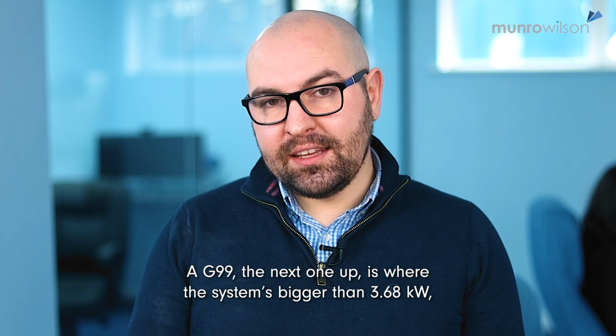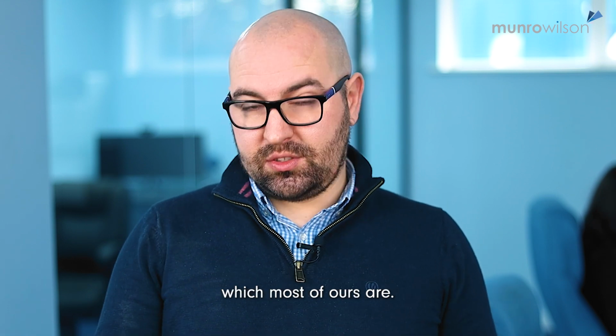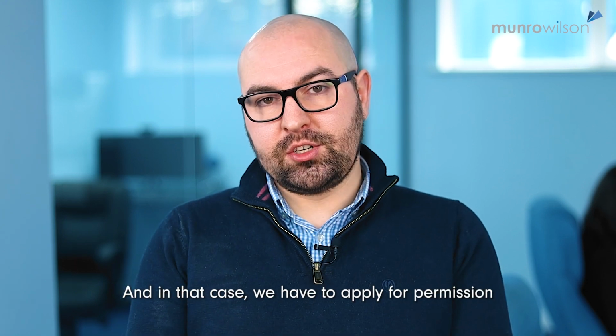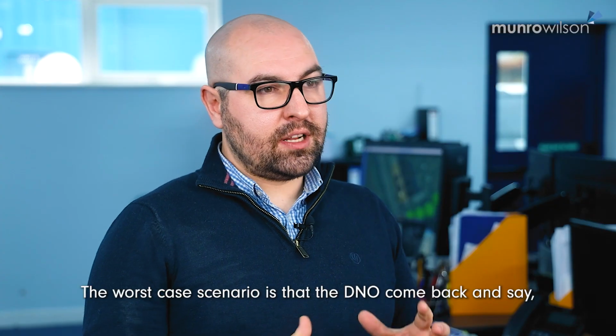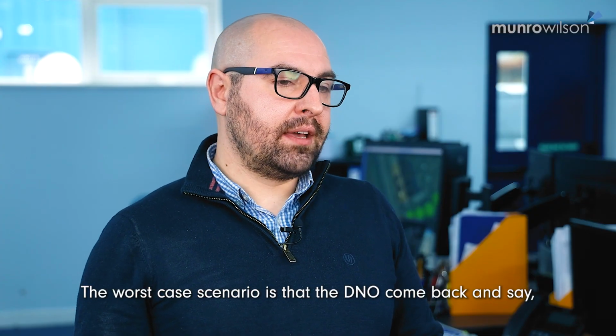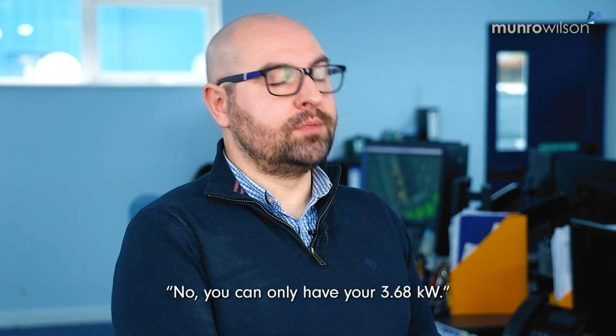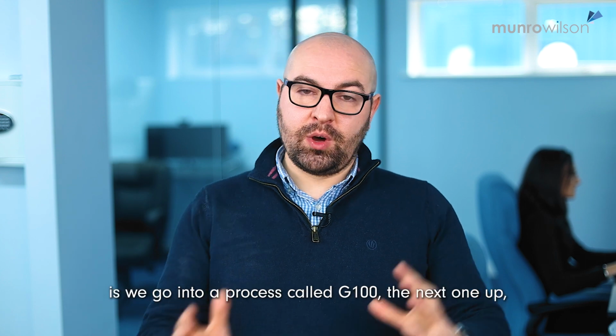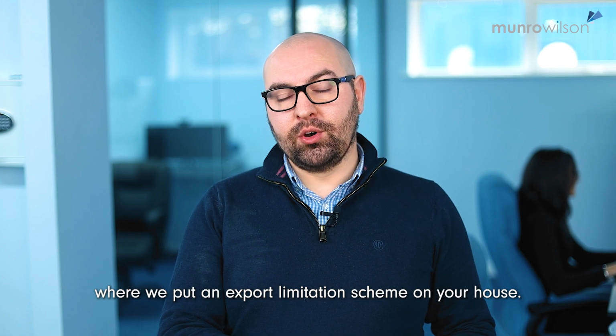A G99, the next one up, is where the system is bigger than 3.68 kilowatts, which is most of ours. And in that case, we have to apply for permission to export that power to the grid. The worst case scenario is that the DNO come back and say, no, you can only have your 3.68 kilowatts. And what we do in that scenario is we go into a process called G100, the next one up, where we put an export limitation scheme on your house.